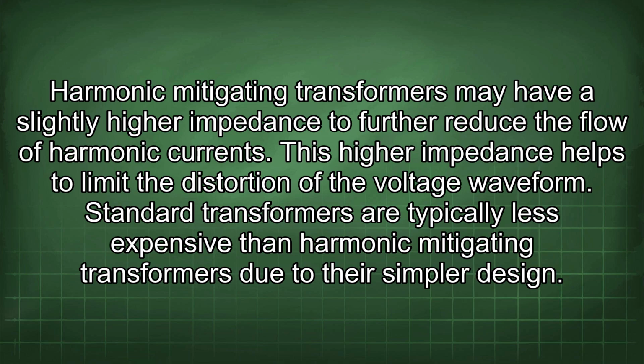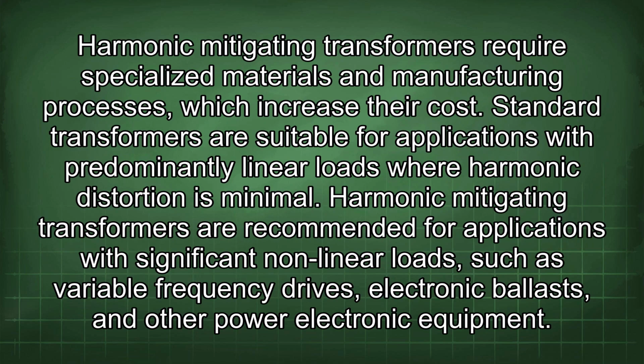This higher impedance helps to limit the distortion of the voltage waveform. Standard transformers are typically less expensive than harmonic mitigating transformers due to their simpler design. Harmonic mitigating transformers require specialized materials and manufacturing processes, which increase their cost. Standard transformers are suitable for applications with predominantly linear loads where harmonic distortion is minimal.